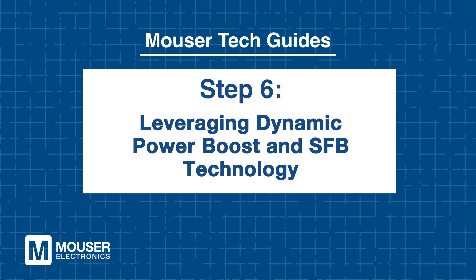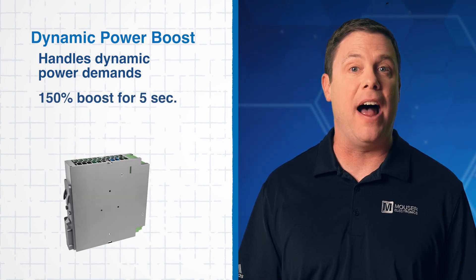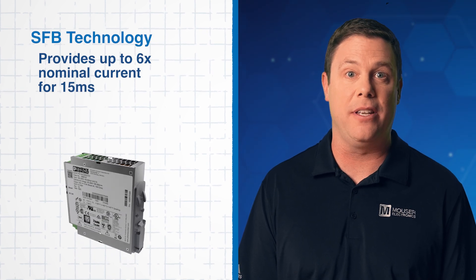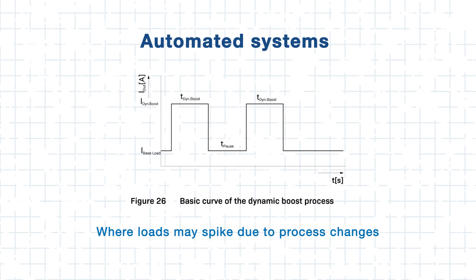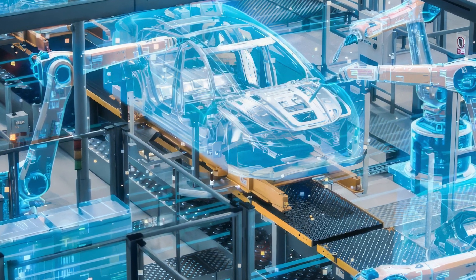Step 6: Leveraging dynamic power boost and SFB technology. The Quint 4 handles dynamic power demands with a boost capability of up to 150% for 5 seconds. Additionally, the selective fuse breaking technology allows the Quint 4 to deliver up to 6 times the nominal current for 15 milliseconds, ensuring quick recovery from overloads or short circuits. These capabilities are especially beneficial for motors and actuators requiring high startup currents and automated systems where loads may surge unexpectedly.